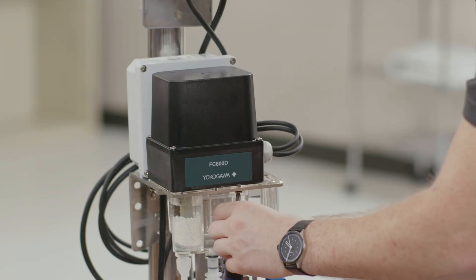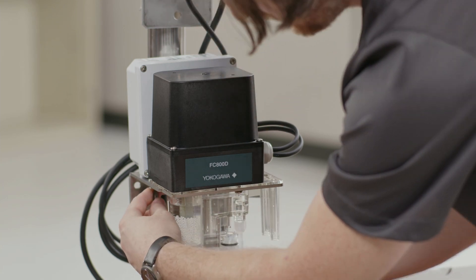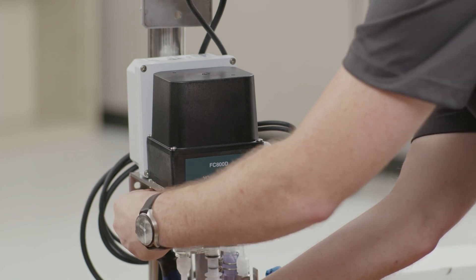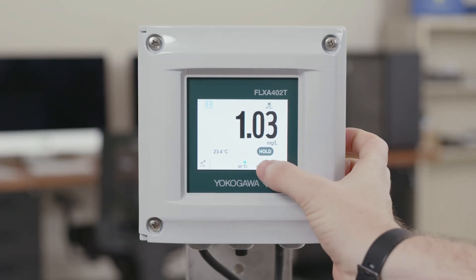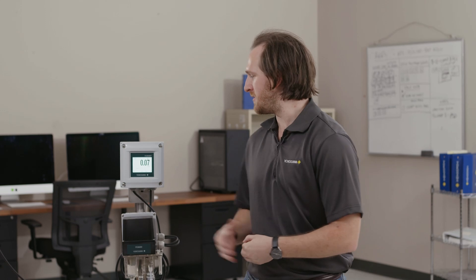Now that we've finished our calibration, we can make sure that the FC-800 measurement assembly is tightened down onto the flow cell and that all process valves are open. If this is the case you can go ahead and turn maintenance mode off and start measuring the process again. Thank you everyone. I hope you now understand how to calibrate your FC-800D.